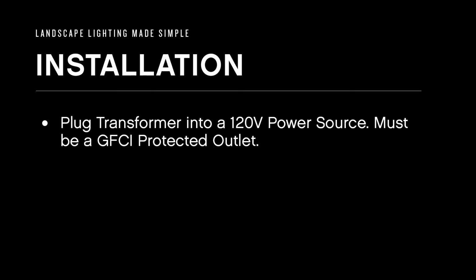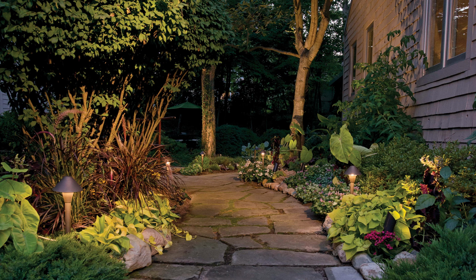After the transformer is secured, it must be plugged into a 120-volt power source that is a GFCI protected outlet. This is in accordance with the National Electrical Code. If you don't have a GFCI outlet, contact an electrician to have one installed. Take the time to check out how everything looks at night to make sure you're happy with the location of each fixture and make any minor adjustments.